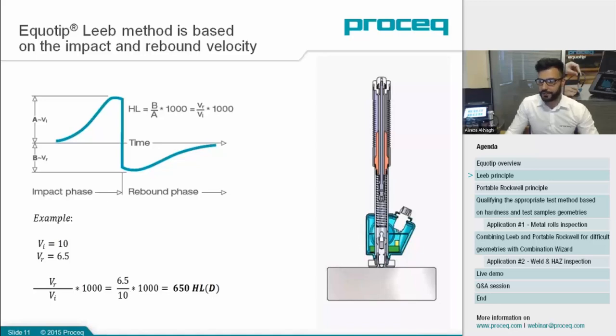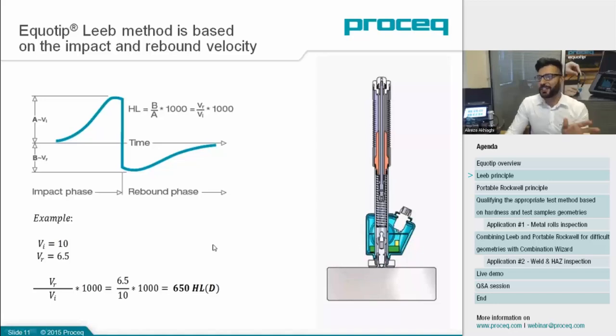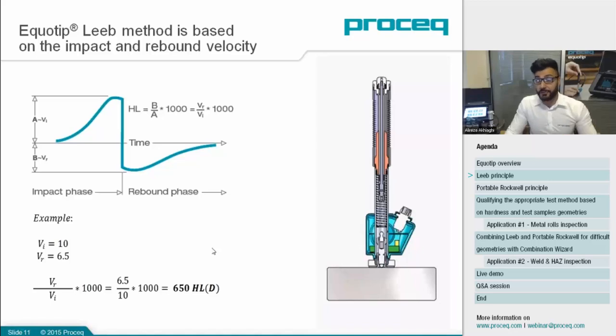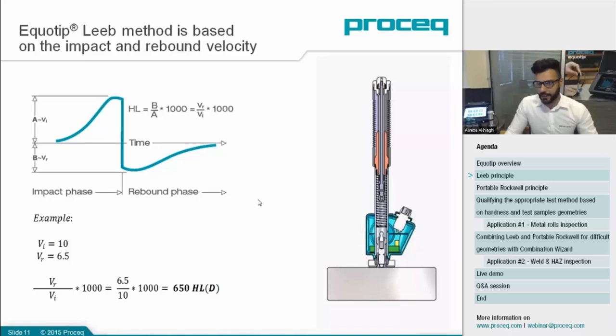The same principle applies to all Leeb devices — they only have different energy and different velocities. That's why you have different Leeb values, and why Leeb G is different from Leeb D: the impact body energy and induction voltage differ. Later on, we'll cover what type of application suits which impact device, and hopefully that will help you make the correct decision during your applications.